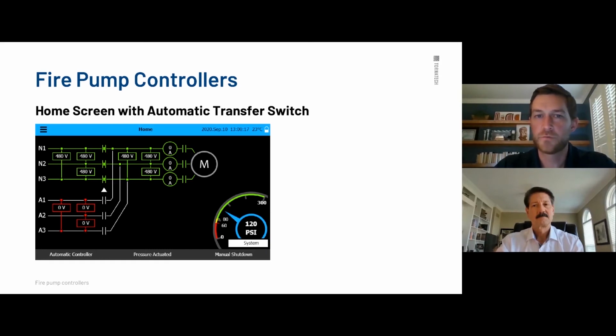We're actually getting 2 readings on voltage for the automatic transfer switch. So we're taking the first one up there at the isolation switch, the incoming power, and then we're going to take another reading right before we get to the motor contactors, just to verify that power is flowing healthily through the whole control panel. So we get 2 readings. Also, it's necessary to get a second reading when the alternate power is on. Since we have 2 power sources, we need to take 2 readings on the voltages.